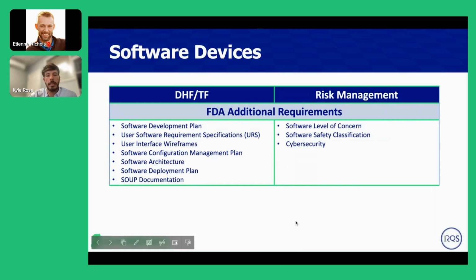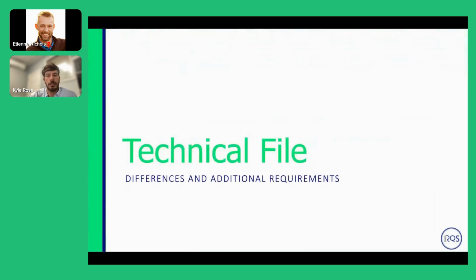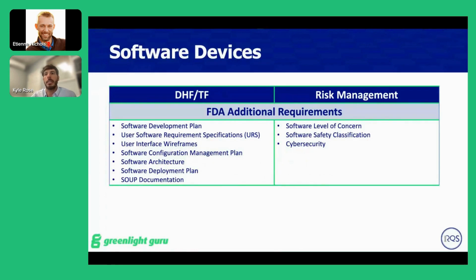One key thing that we'll touch on a little bit in the 510K area is that with some devices, the user needs and inputs might not need to be shared with the FDA, and the risk analysis in some cases is not part of your 510K. But for software devices, that information will be included.